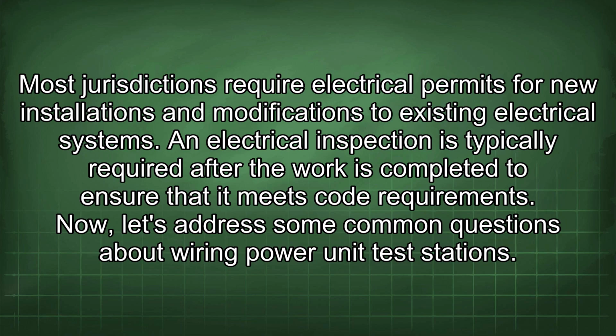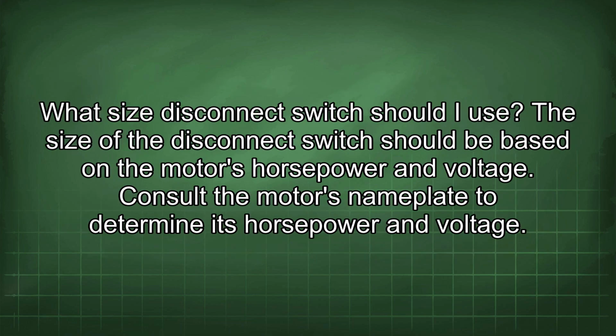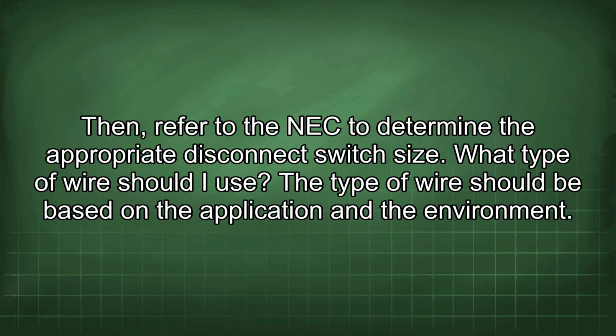Now, let's address some common questions about wiring power unit test stations. What size disconnect switch should I use? The size of the disconnect switch should be based on the motor's horsepower and voltage. Consult the motor's nameplate to determine its horsepower and voltage. Then refer to the NEC to determine the appropriate disconnect switch size.